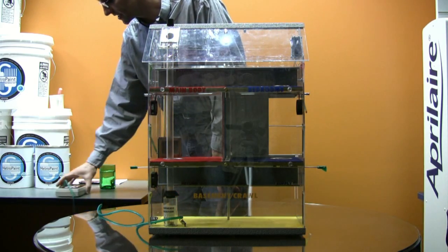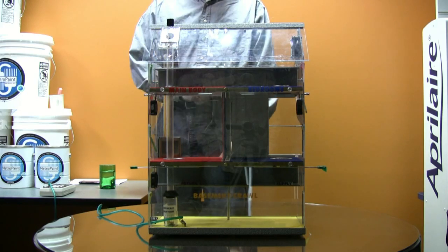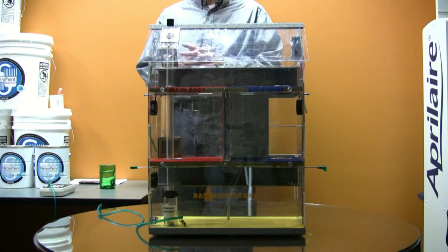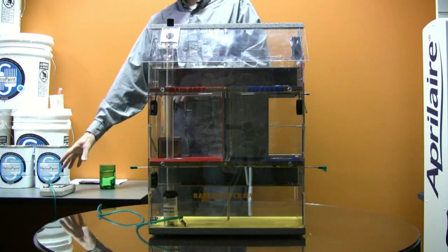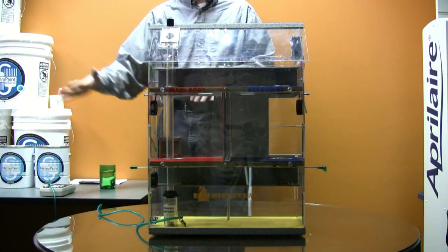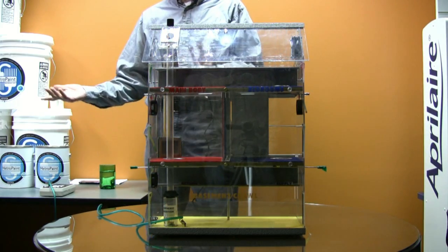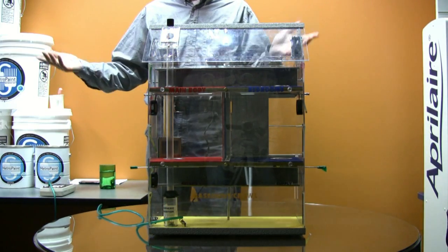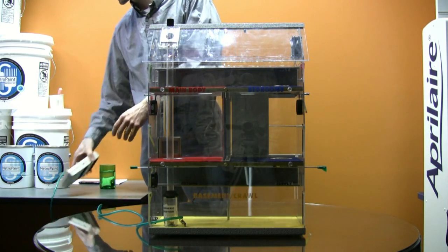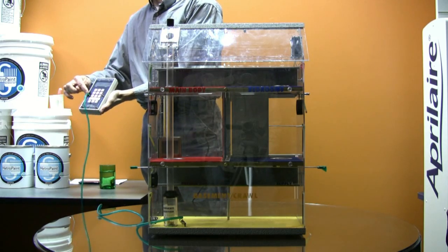I have a manometer set up here. Does anyone know what a manometer does? It measures pressure, in pascals. It measures differences in pressure. Originally manometers were tubes of water, and in one place you had greater air pressure and it would push the water column further up in the other area. That's why we actually measure air pressure in inches of water column. But these are all electronic, and we have 2 ports. It's measuring the difference between this port and that port.